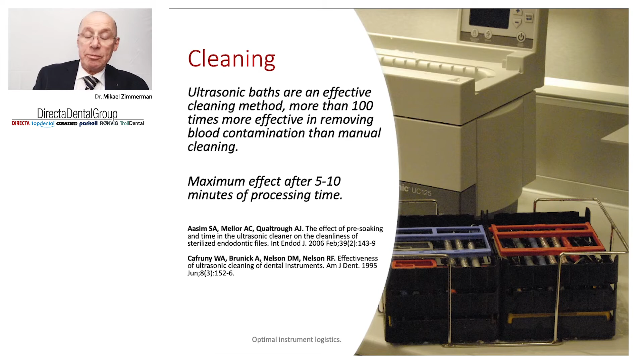In some ultrasonic baths, you can use a cleaning solution, and there are also different solutions that you can use for cleaning and disinfection within the ultrasonic bath. What you must keep in mind is that the ultrasonic solution can become increasingly contaminated with debris after each successive load of instruments that are being cleaned. So instruments should be thoroughly rinsed after sonication in preparation for sterilization.